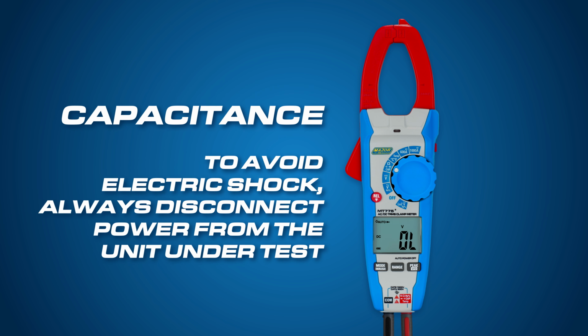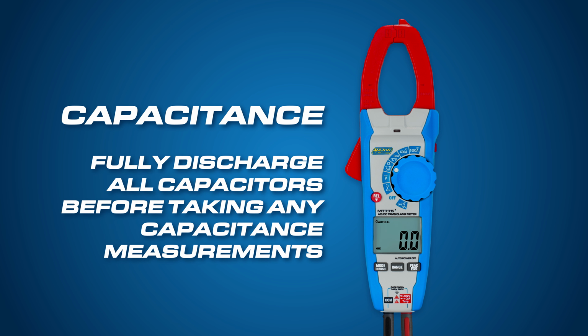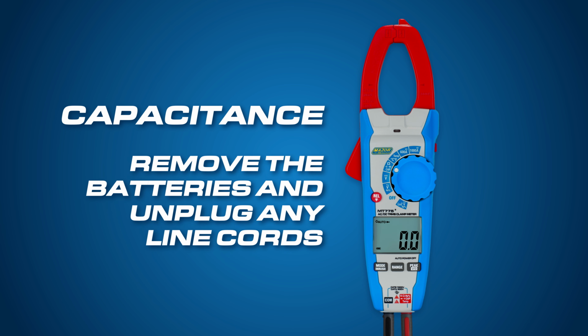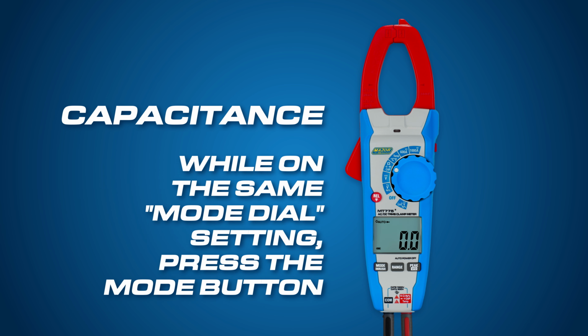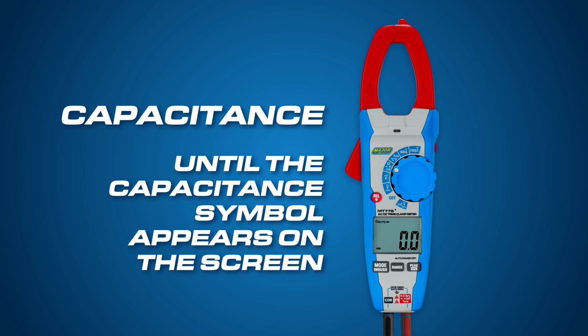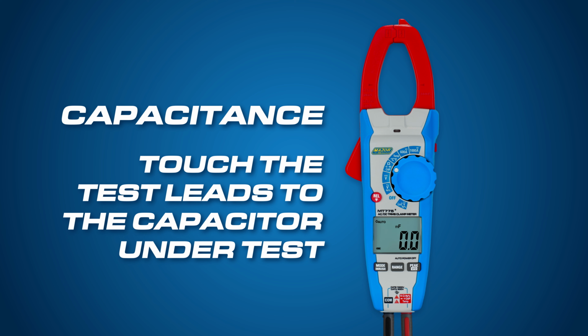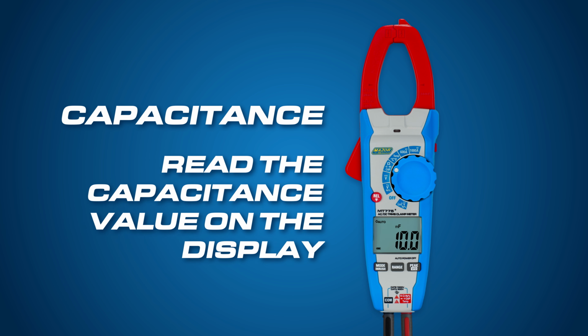To avoid electric shock, always disconnect power from the unit under test and fully discharge all capacitors before taking any capacitance measurements. Remove the batteries and unplug any line cords. While on the same mode dial setting, press the mode button until the capacitance symbol appears on the screen. Then touch the test leads to the capacitor under test and read the capacitance value on the display.